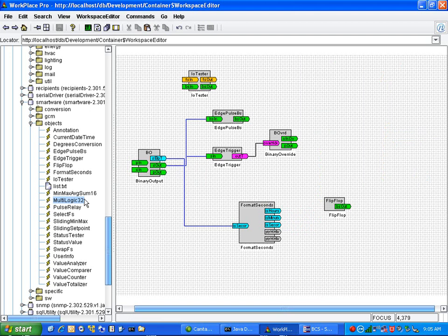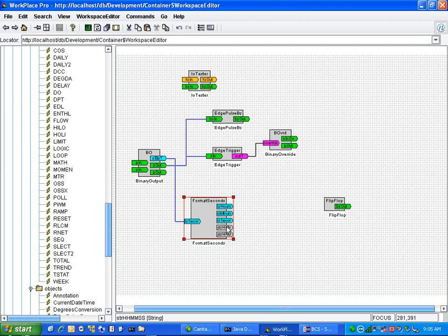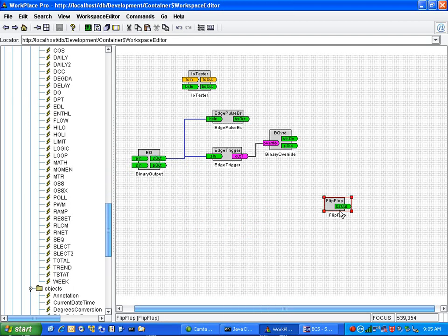What's nice is the high-low in the GCM container. There's the old-fashioned high-low that works very nice. You have up to 8 inputs on that one. The interesting thing about the GCM, if anybody did a lot of Network 8000 programming in the past, a lot of times if I need a simple T-stat block, I resort to the T-stat block in here because I like the deadband in it, and we don't have any place else that has a normal T-stat.